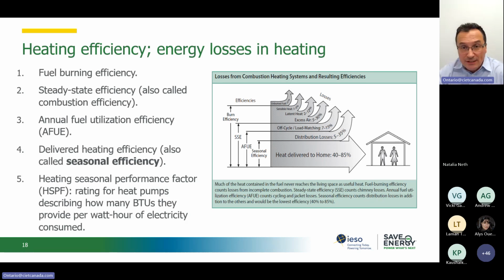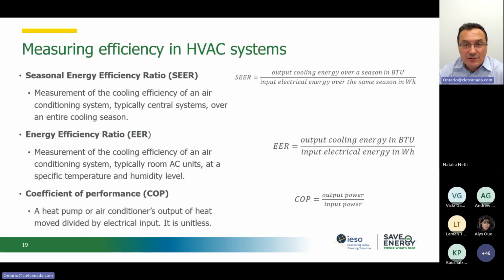So first of all, you see it is not even using the same units of measurement. And that's coming from how we defined efficiency in the cooling systems for quite a long time now. Very common to see this in literature. Manufacturers, again, used various indicators. We used the energy efficiency ratio, popular with many equipment manufacturers because it's easy to replicate the numbers in control conditions. But what we are interested in from our perspective as users is the seasonal energy efficiency ratio.